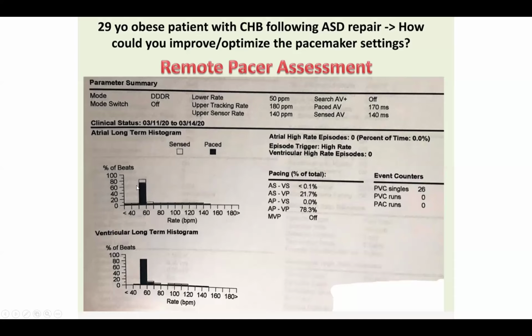So that gives you an indication of two things. One, that he's probably a fairly sedentary person, and two, that the rate responsive sensitivity on the device is very poor. There are different ways that pacemakers can detect activity. Medtronic devices, which this seems to be, have a piezoelectric crystal that can feel activity in motion and will slowly increase the rate. Some devices can use body wall impedance changes. Some of them actually have temperature probes on the lead that can assess small changes in body temperature as a way of increasing the heart rate.